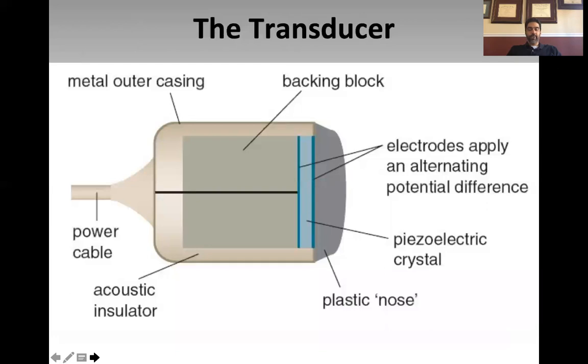First, let's talk about the actual hardware itself — specifically the ultrasound probe. If you were to take the ultrasound probe and sort of cut it down the middle, break it apart and look inside, this is a representation of what you would see. Please do not do this with any of our probes. What you would see inside is a housing which contains the core of the probe, which is the piezoelectric crystal.